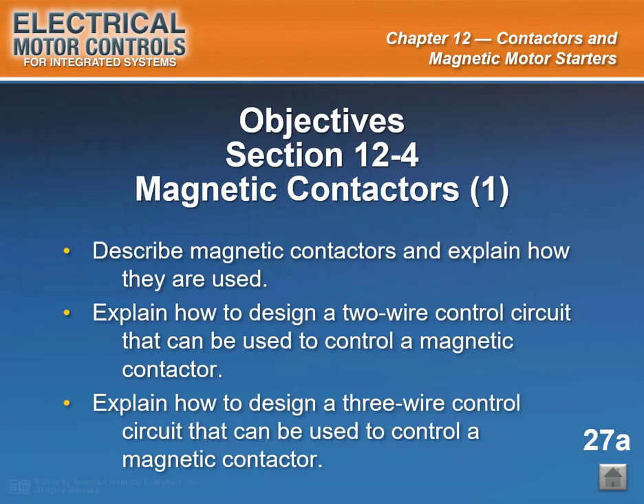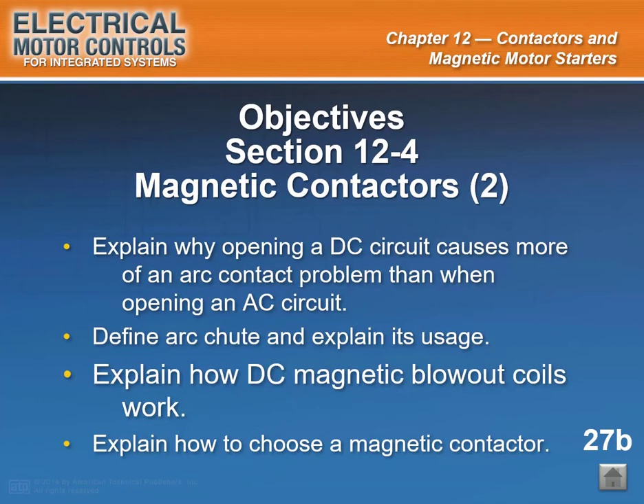Slide caption, Objectives. Section 12-4. Magnetic contactors. By the end of this presentation, you should be able to describe magnetic contactors and explain how they are used. Explain how to design a two-wire control circuit that can be used to control a magnetic contactor. Explain how to design a three-wire control circuit that can be used to control a magnetic contactor. Explain why opening a DC circuit causes more of an arc contact problem than when opening an AC circuit.